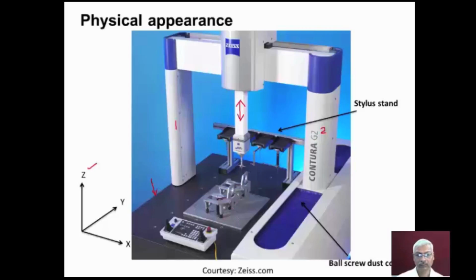We can move the stylus in x, y, and z directions by operating the joystick. You can see the joystick, and various subroutines are available. We can select the subroutines by using this keypad, for example, measurement of the diameter of a hole, or the angle between two surfaces. Like this, the appropriate subroutine is selected, and then the data points are collected. We can observe a stylus stand here directly mounted on the surface of the granite table. This stylus stand holds styluses of different sizes.